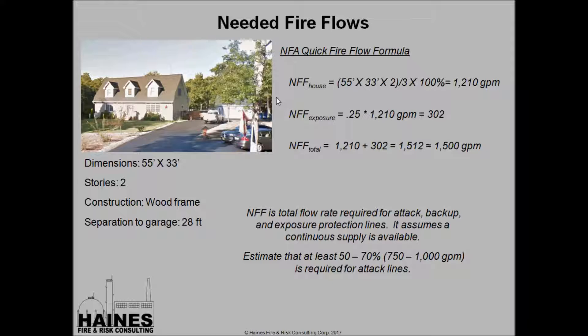The NFA quick fire flow formula is one of my favorites because it's very easy to apply in the field. You simply calculate the floor area of the building, divide that by three, and multiply it by the percentage of involvement, which gives you your GPM recommended for the structure. In this case, we have a 55 by 33 foot building that's two stories tall, divide that by three, times 100, and we end up with 1,210 GPM for the house.